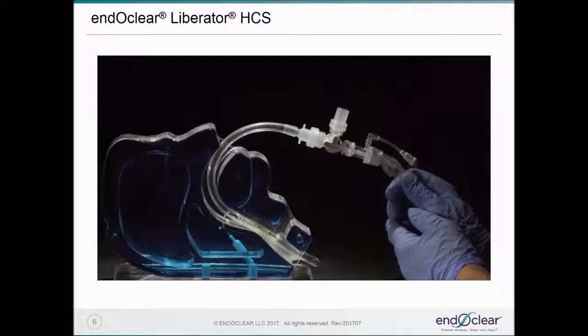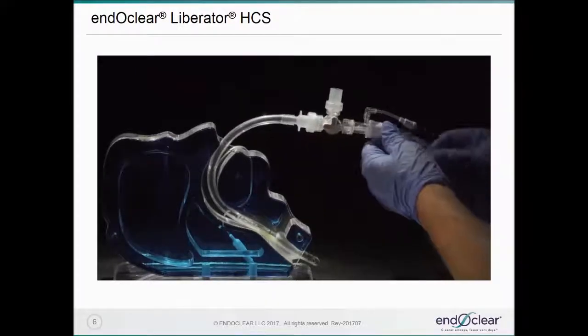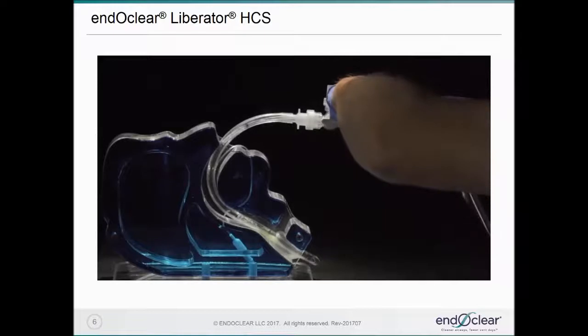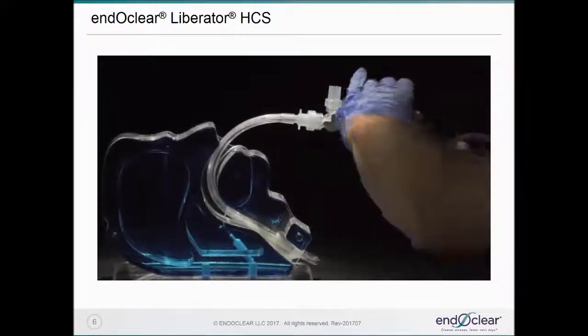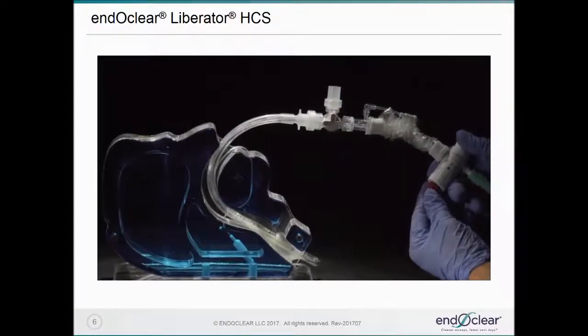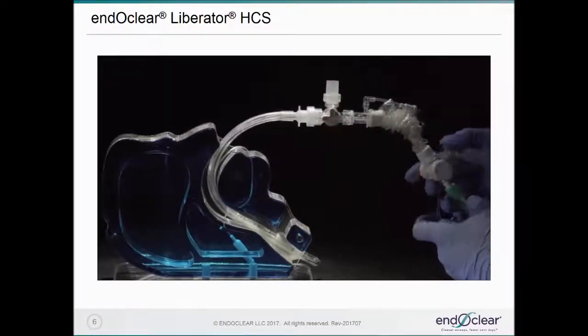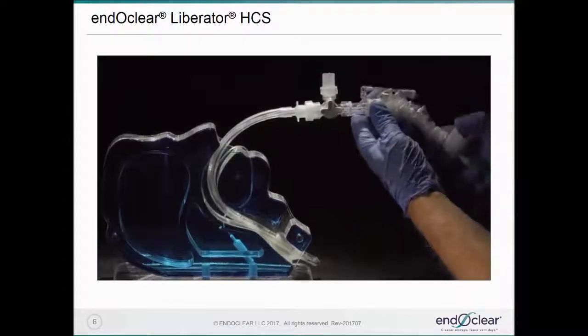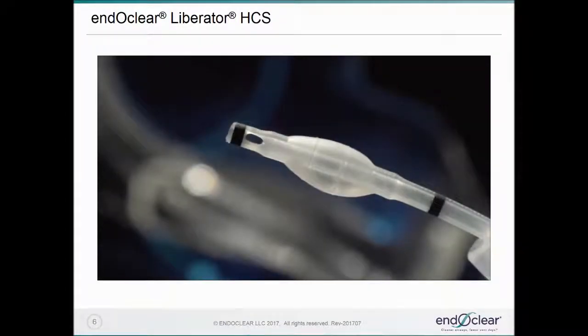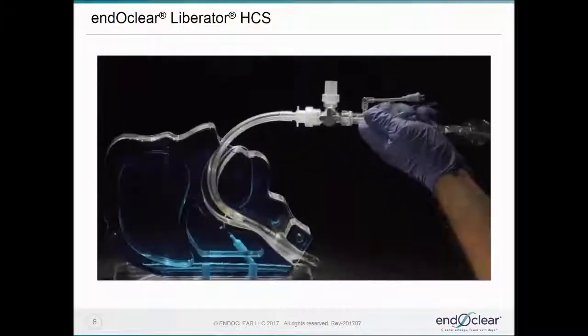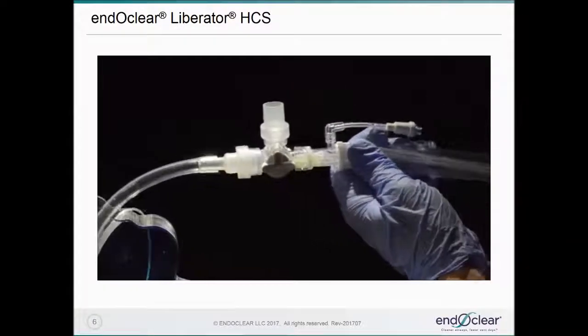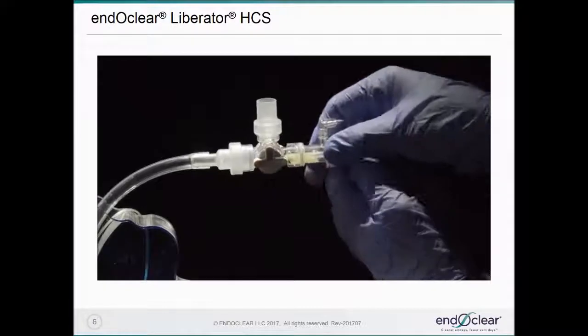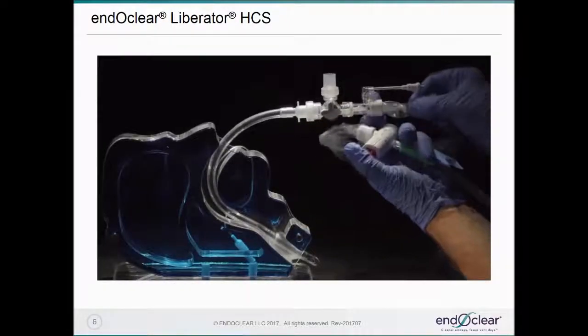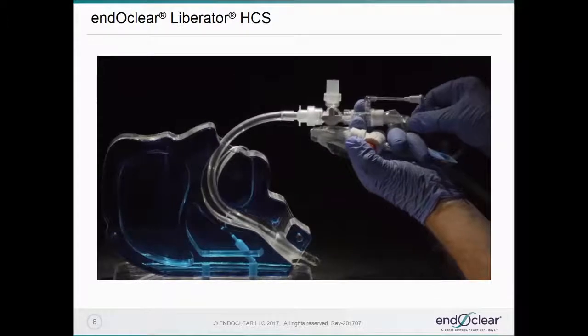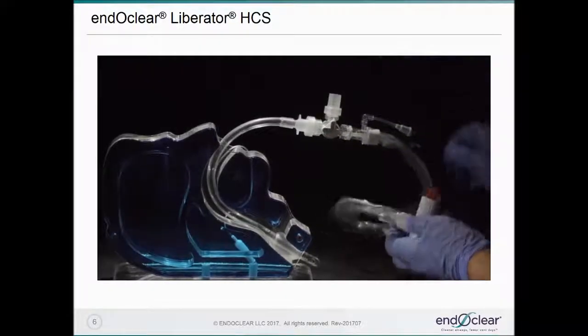So what we are going to do now is to pass the ENDOCLEAR device in the same way, and we are going to turn the controller to wiper only. Now we're going to inflate the wiper and then pull it back into the cleaning chamber. And now I'm going to go to suction and apply suction to get any of the material that's residual in the manifold.